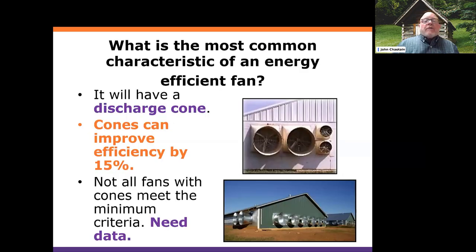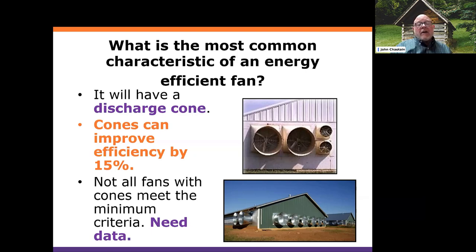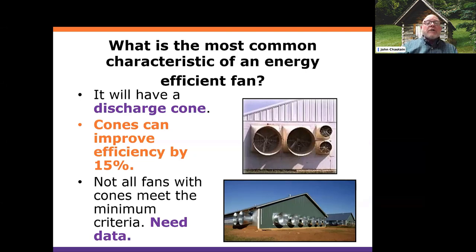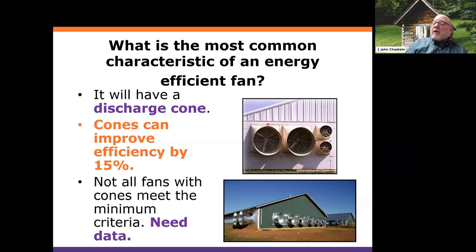What does an energy efficient fan look like? A basic characteristic is that it will typically have a discharge cone — that's what you're seeing in these pictures: some nice shiny galvanized ones and some old plastic ones. Several years ago we did a paired comparison using BESS Lab data, testing a fan with the exact same shutter and housing both with and without the cone. On average, the cone improved efficiency — the VER number — by 15% at one-tenth of an inch static pressure. However, not all fans with cones meet the minimum criteria we're going to talk about.